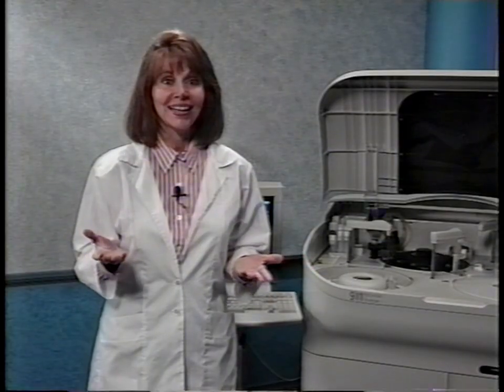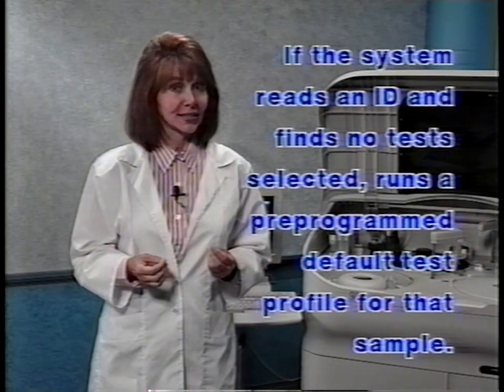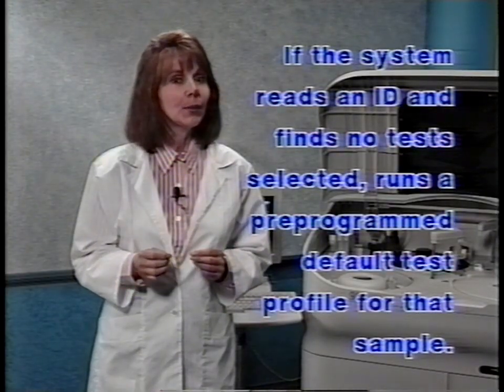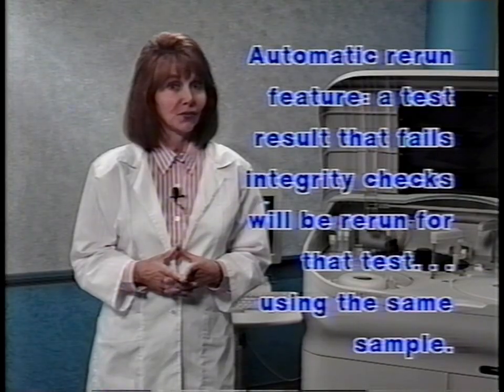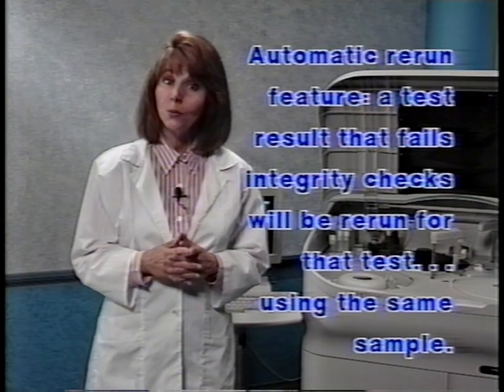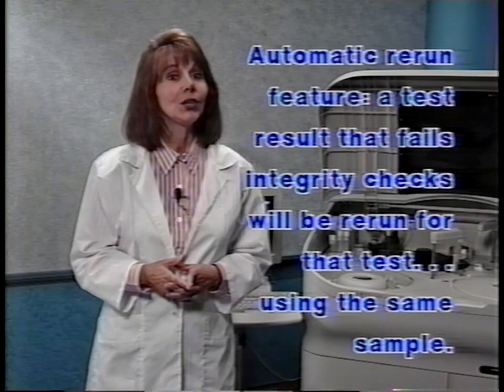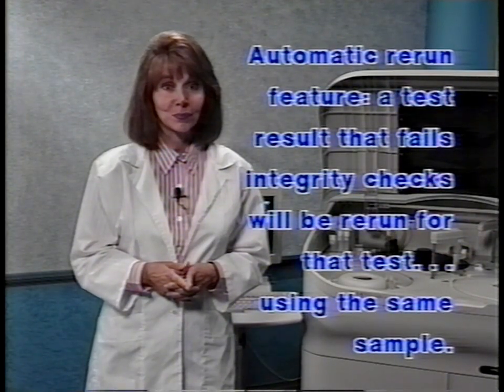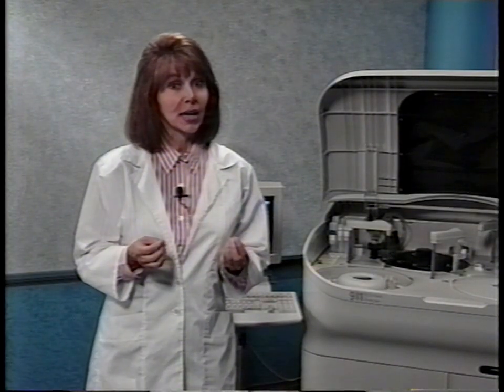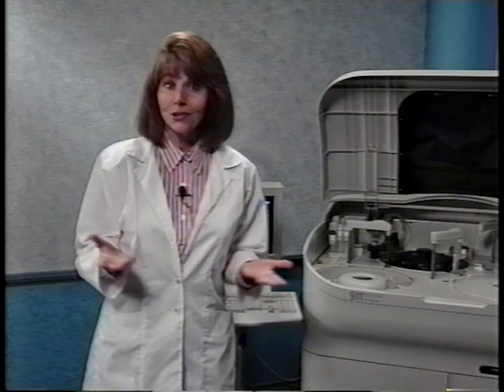And here's a feature you'll like. If the system reads an ID and finds no tests have been selected for that sample, it runs a pre-programmable default test profile for that sample. The analyzer also has an automatic rerun feature. When this is selected, a sample having a test result that fails any of several integrity checks will be rerun for that test. The rerun is performed using the original sample without any operator intervention. During sampling of the rerun, the system assesses whether it should pipette a larger or smaller amount of sample for a test. When the test is completed, the result is automatically multiplied by the correct factor before the rerun report is printed. You'll find that with the 911, the occasions when you need to manually dilute samples are greatly reduced.